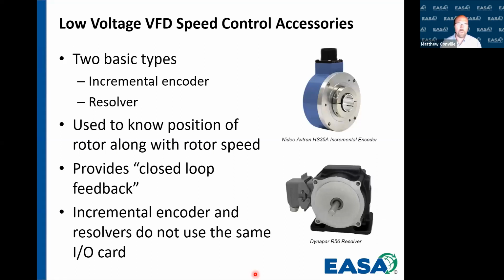So some of the most simple ones are going to be speed control accessories. There are two basic ones that we most commonly see for speed control, and that's going to be an incremental encoder and a resolver. So here's an example of a Nidec Avtron light mill duty incremental encoder. And here's an example of a Dynapar heavy duty R56 resolver. And what these do is they actually tell us the rotor's position along with the rotor's speed at any instant in time. It's going to give us what we call closed loop feedback.